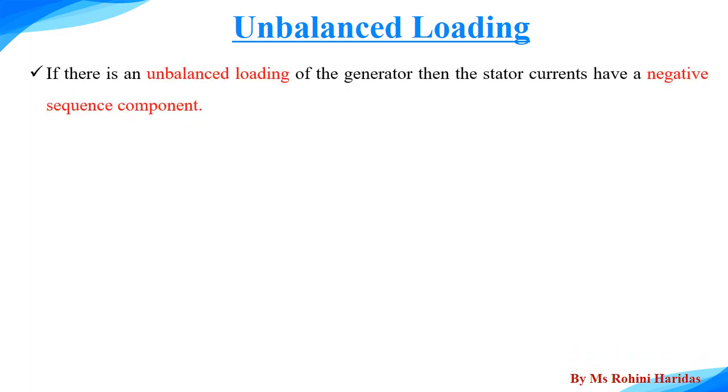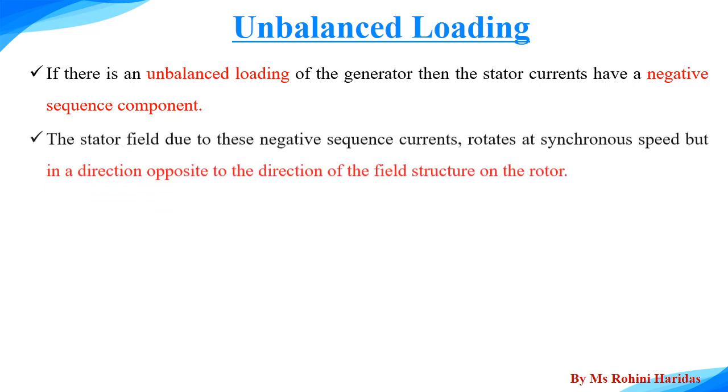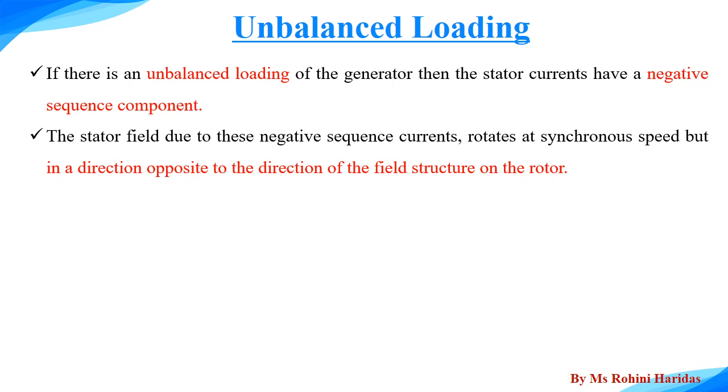Unbalanced loading. If there is an unbalanced loading of the generator, then the stator current have a negative sequence component. The stator field due to this negative sequence current rotates at a synchronous speed but in the direction opposite to that of the direction of field structure on the rotor.